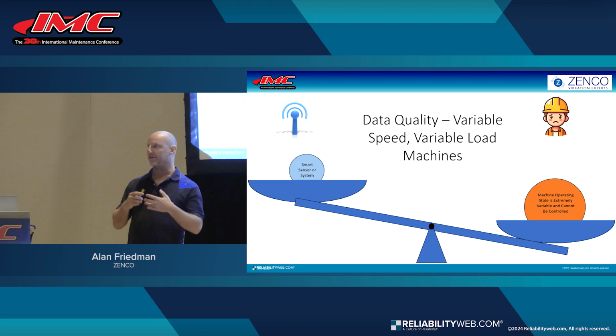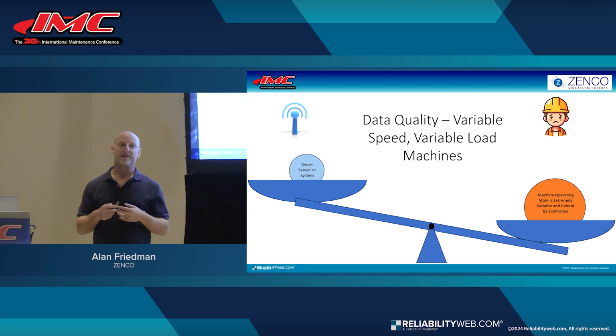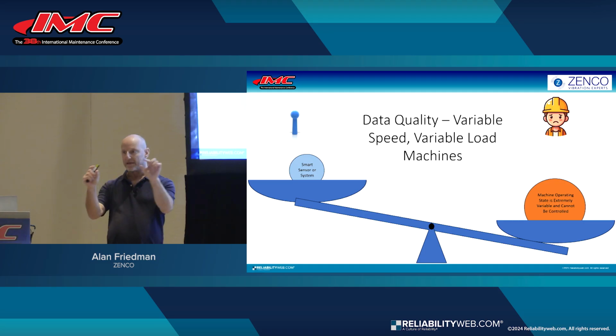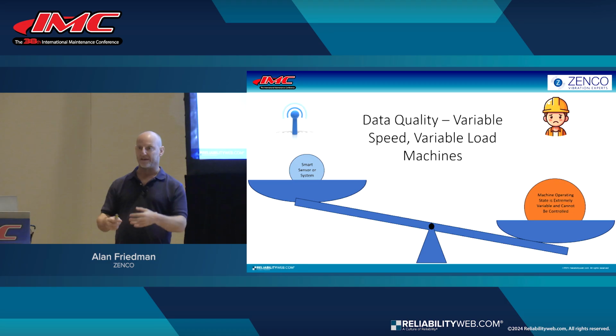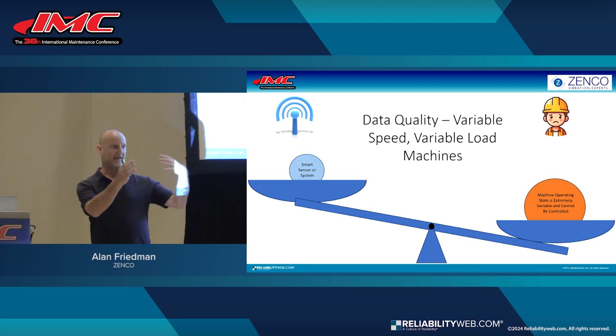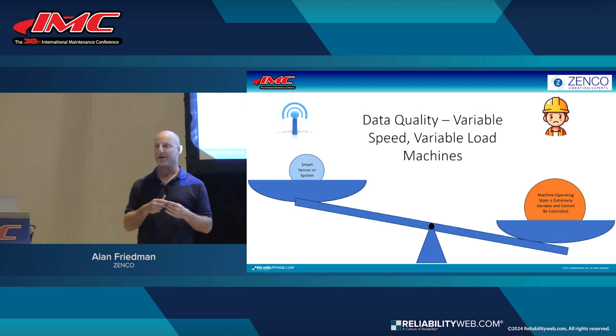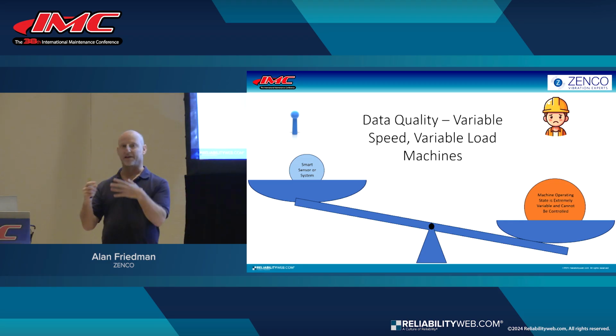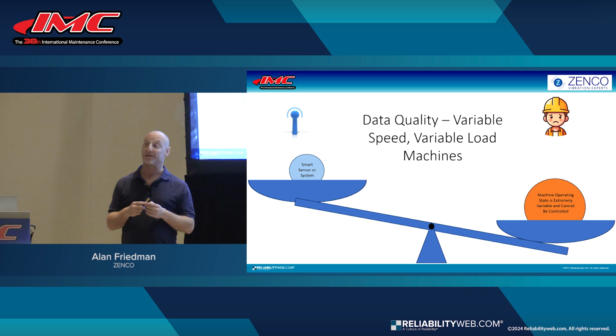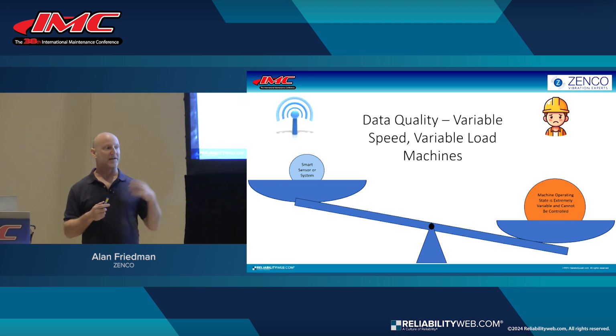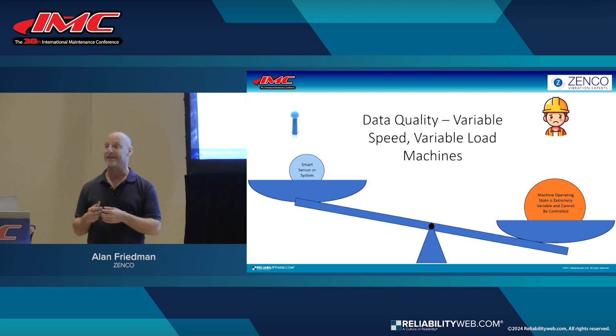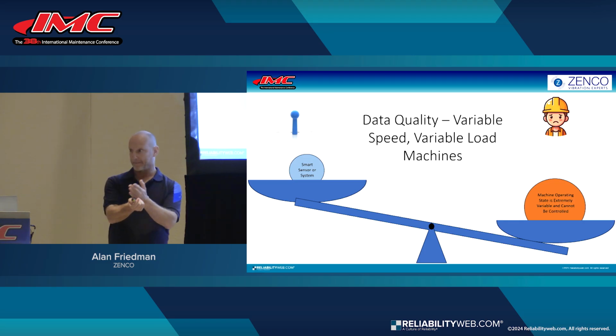Maybe these are all going into a SCADA system or a Pi database, all time-stamped. A smart system could look at all the timestamps and say, during that test this was in this operating state, so it goes in the apple basket. Then three hours later it's in another state, so it goes in the orange basket. So a smart system could potentially, even if it wakes up every hour regardless of condition, sort the data on the back end and get repeatable readings.